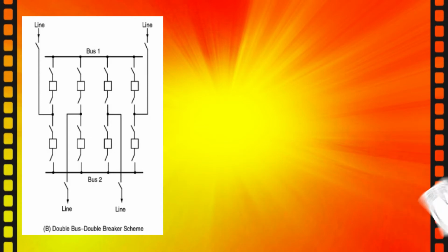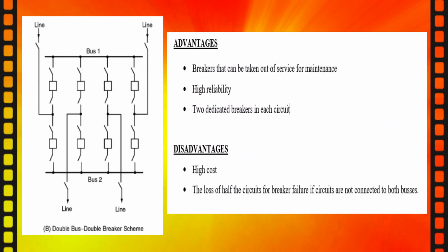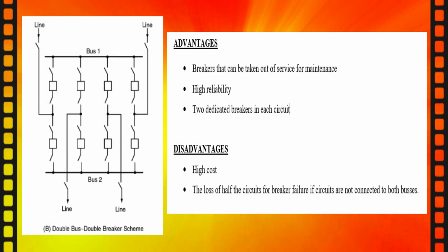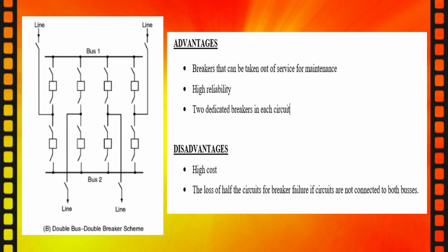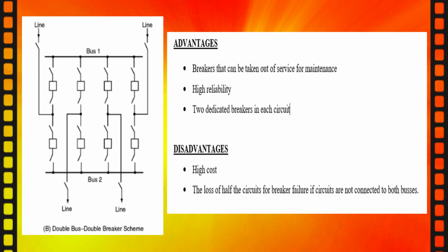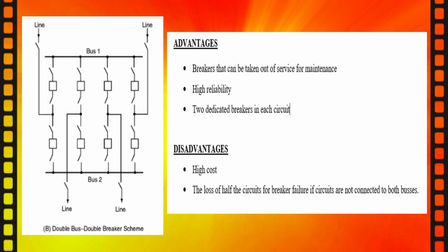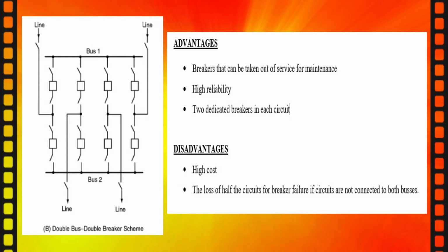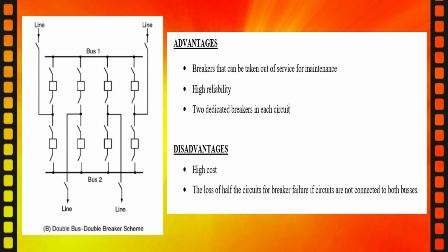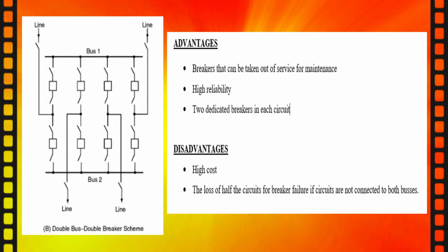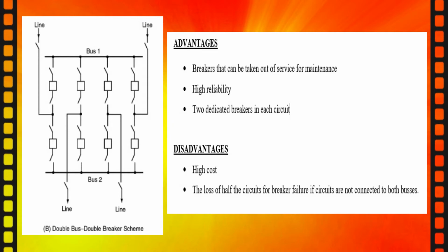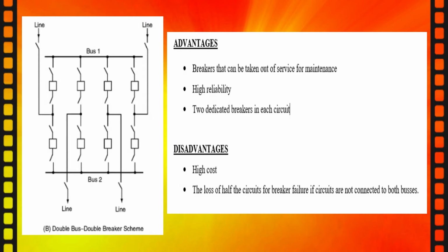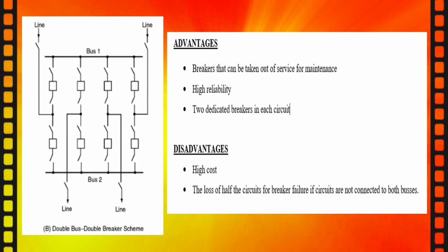The advantage of this diagram is that a breaker can be taken out of service for maintenance. Second is high reliability. Then there are two dedicated breakers in each circuit for this diagram. Okay, for the disadvantage, the cost is high. And the second is the loss of half the circuit for a breaker failure if the circuits are not connected to both buses.